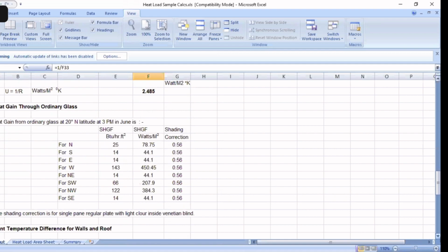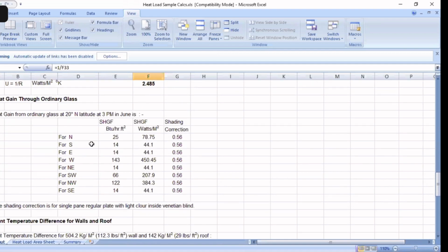Solar heat gain through ordinary glass. Solar heat gain factor, there is for direct solar radiation. North wall is this. We have considered 20 degree north latitude for Calcutta at 3 p.m. on June. From there I have taken the solar heat gain factor. This data I have taken from the Carrier handbook, and I have converted it into watts per meter square, because the Carrier handbook gives BTU per hour per foot square. So I have converted it, and then I have considered light color Venetian blind.